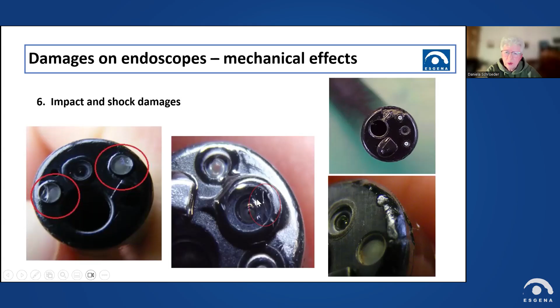If you have an unfortunate situation with a short shock, which means just shortly touching another surface, processor, or the environment in the procedure room, it can happen that the lens system, we call it the video chip, has some damages. There are 5 lenses glued together, and especially here you can have some breaks. It's not visible in the leakage test because it's too small. Even bubbles in the visual check of the leakage test won't show it. But what you will see is a blurry image or black spots.